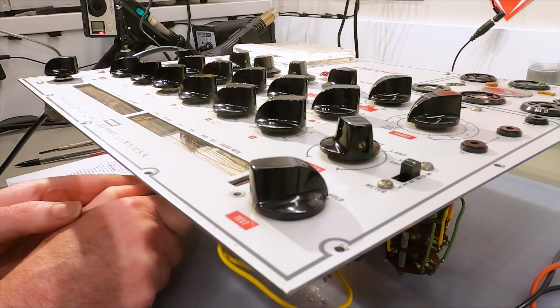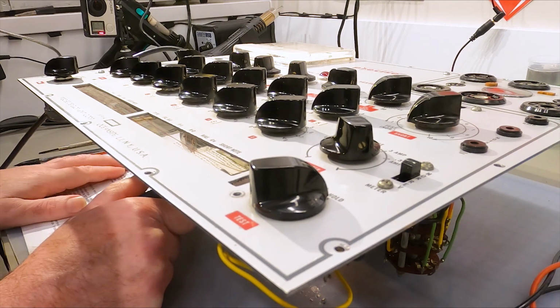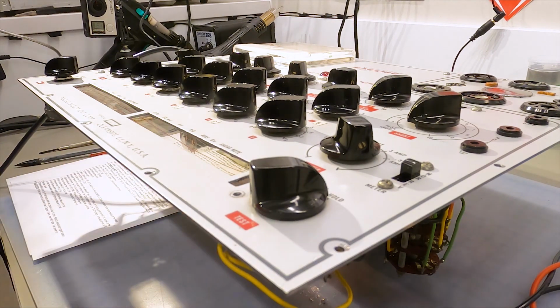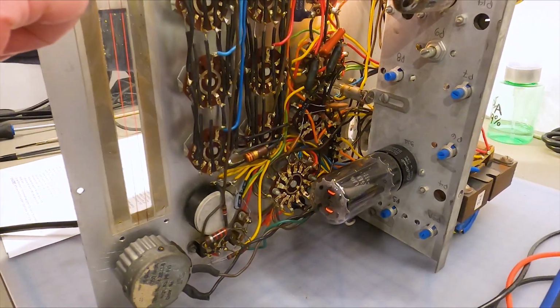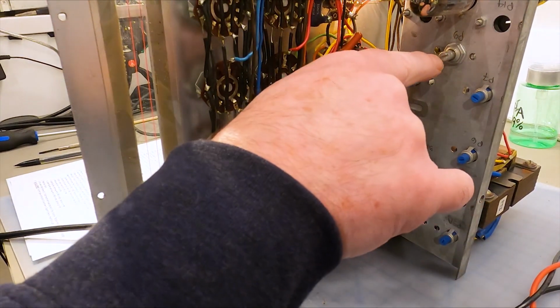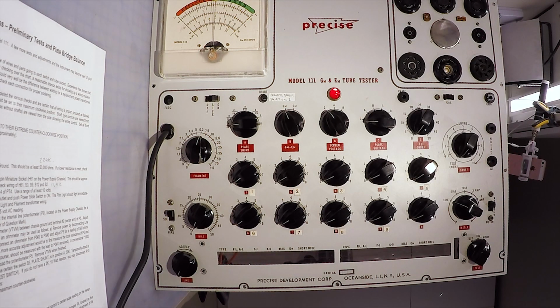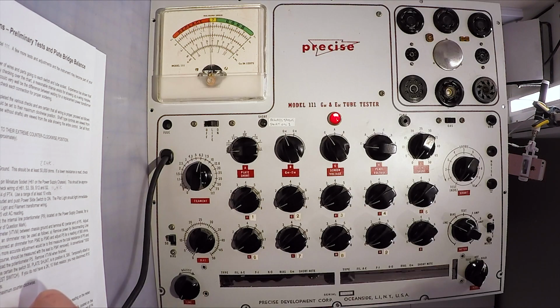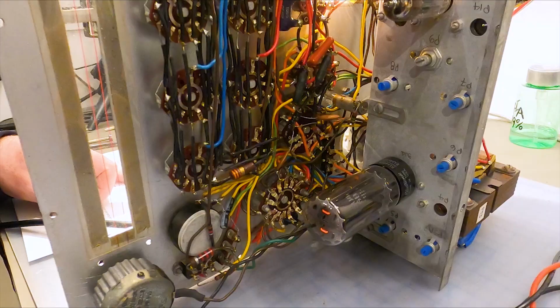However, we can get closer by adjusting P9. We'll do that. And we've done that. I'll tip this back up so we can see what we're doing. Again, this was P9 that I adjusted to get the center position on the meter, which again is not quite at center because we have the instrument tipped on its side. So we're about 1 mark to the left of center on the top scale, which is the GM scale. So we're at step 13.